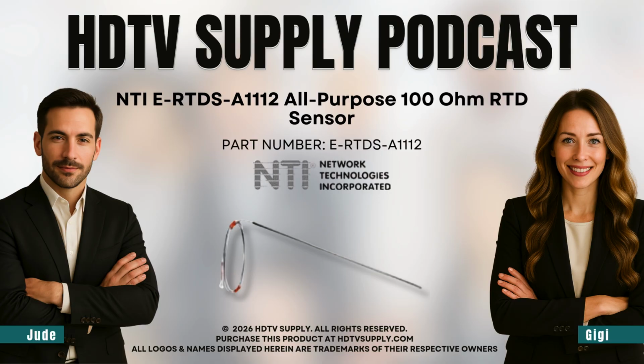So to sum it all up, for about $270, you get this incredibly tough stainless steel sensor that has certified precision over a really useful range. You're buying versatility. But the most interesting detail for me is that design asymmetry we found. Look at the transmitter. That E-RTDT-1562 transmitter can handle temperatures all the way up to 1,562 degrees Fahrenheit. Which is way hotter than the sensor's own limit of 1112.